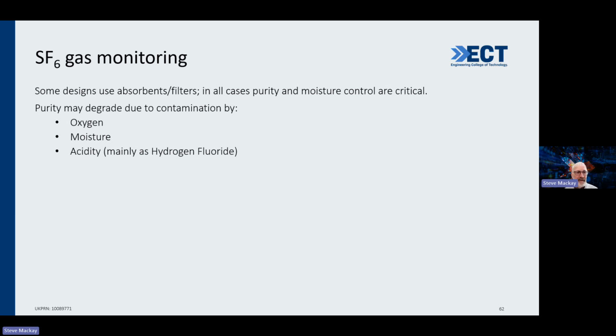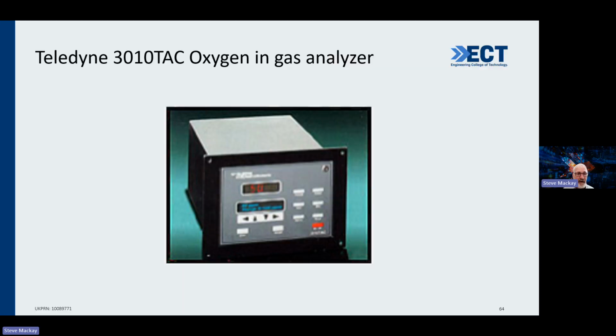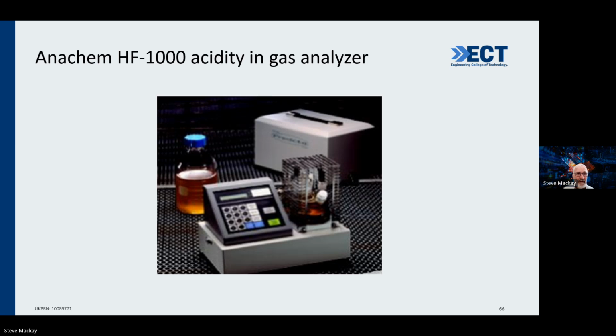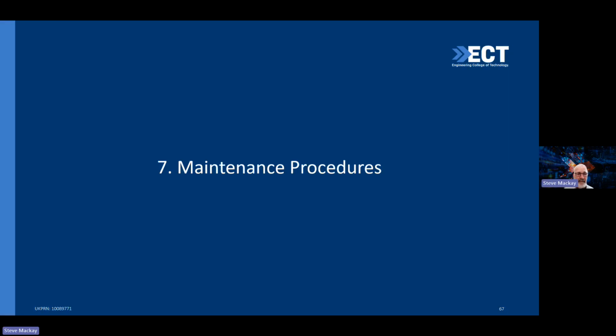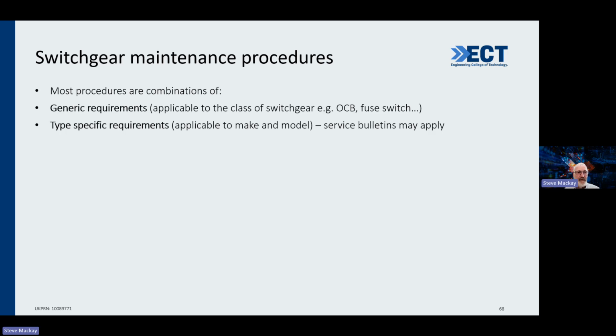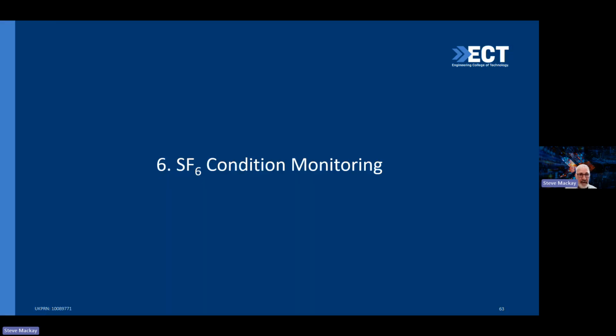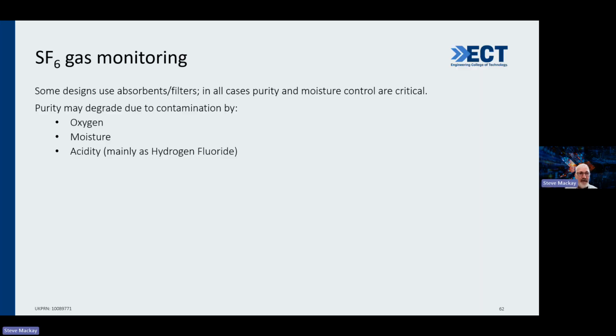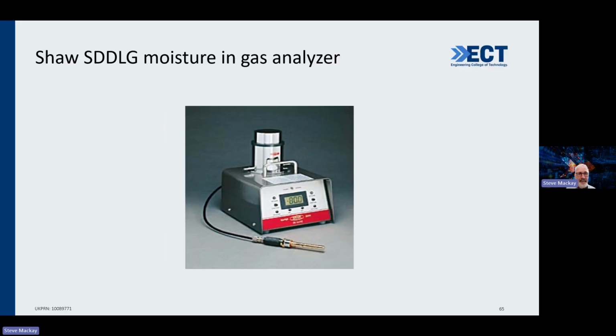But let's talk about SF6 because we've still got a lot of them installed. So purity may degrade due to contamination by oxygen, moisture, and acidity. Hydrogen fluoride, so you've obviously got to watch out for that. So there's a bit of condition monitoring of SF6 acidity, and again, I don't want to mention all the bits of equipment, but there's quite a lot of testing that you can do. The testing you would be doing with SF6 relates to the oxygen, fluoride, moisture, and acidity. Those are the things we'd be looking for.